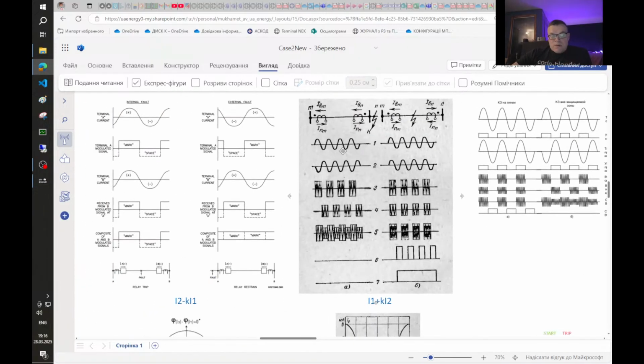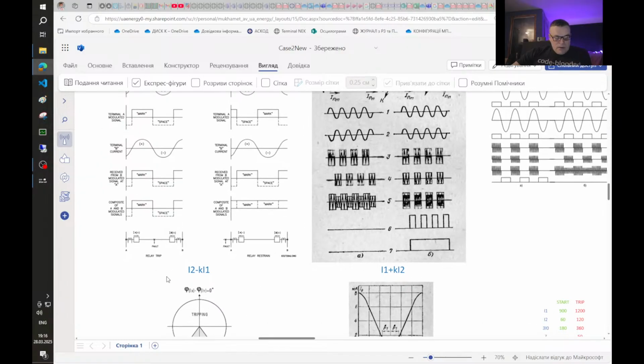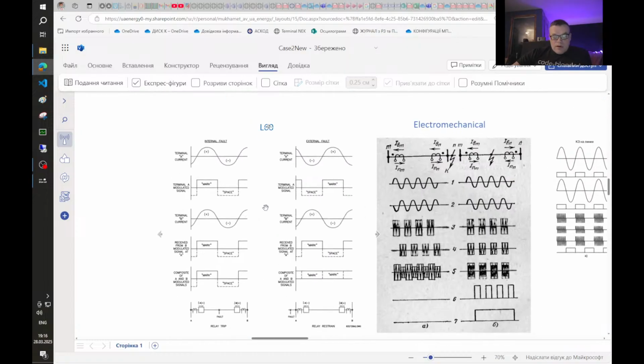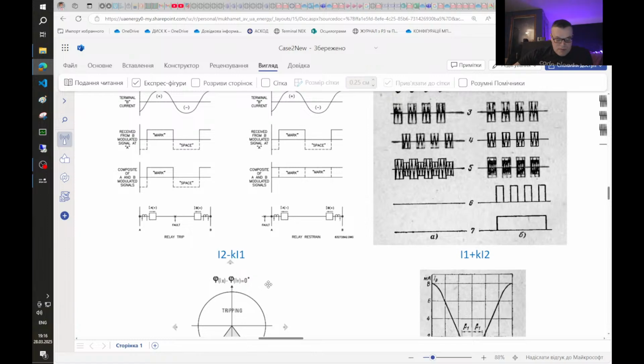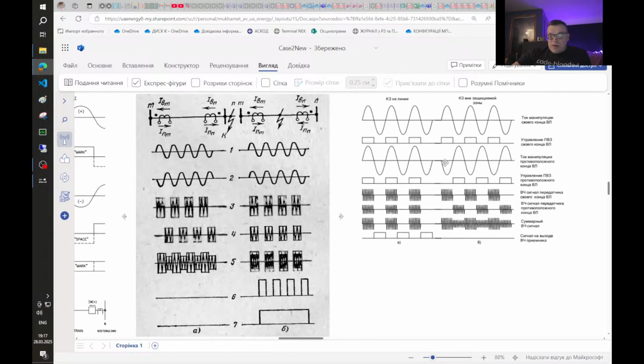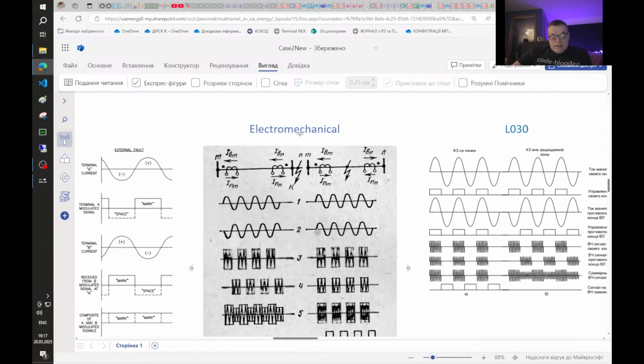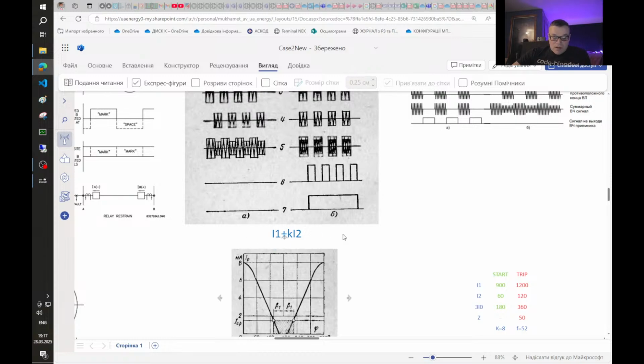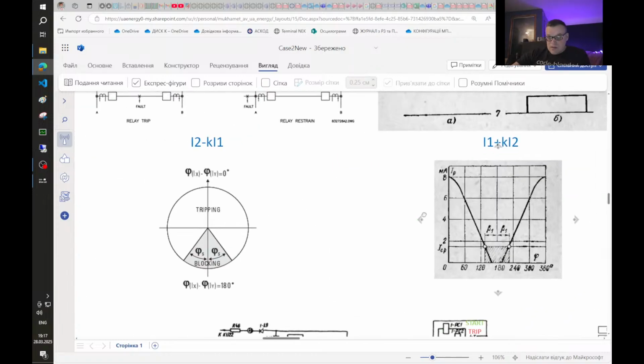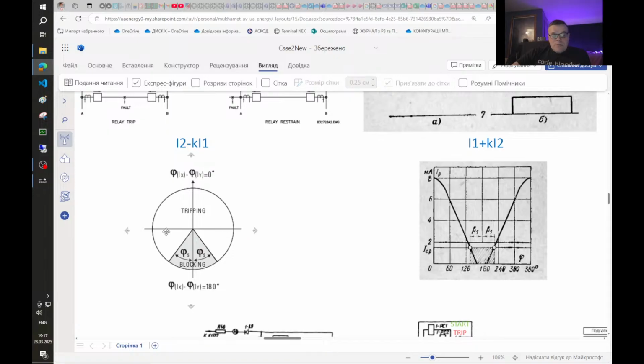So usually for this phase comparison, not phase currents or line currents are used, but a mixed signal. For the L60 this is a combination of negative sequence current and positive sequence current. So the equation looks like this: negative sequence current minus a coefficient times positive sequence current. But for the L30 and for our old electromechanical protections, these equations are usually used. This picture also shows when protection initiates a trip.